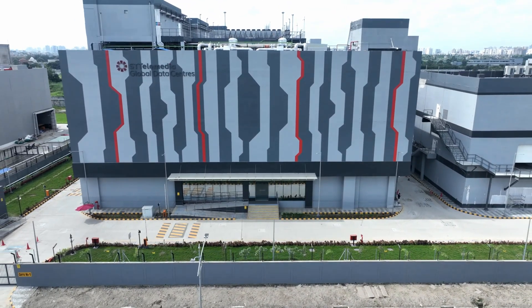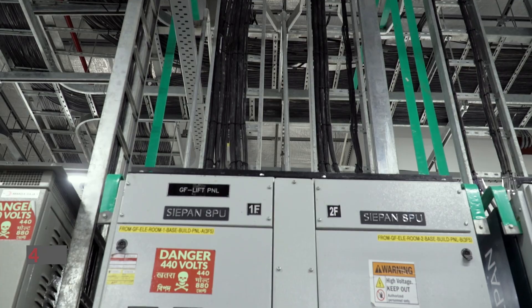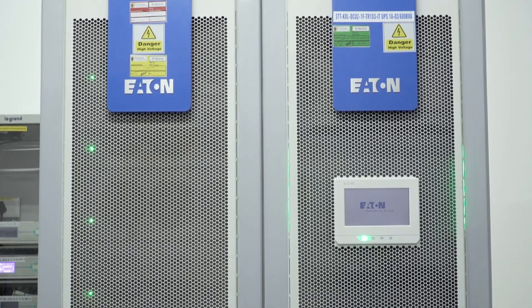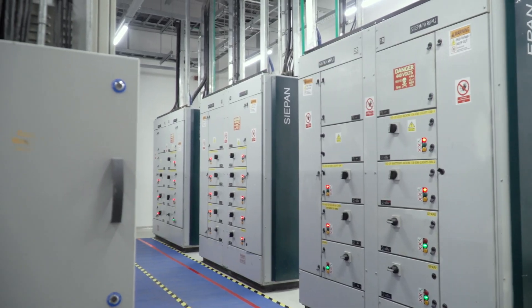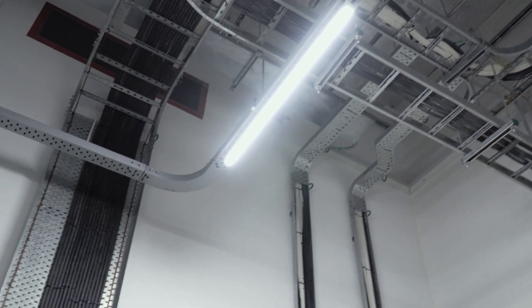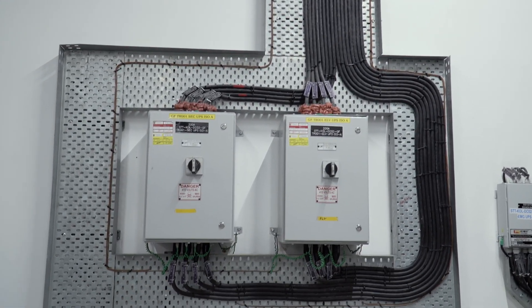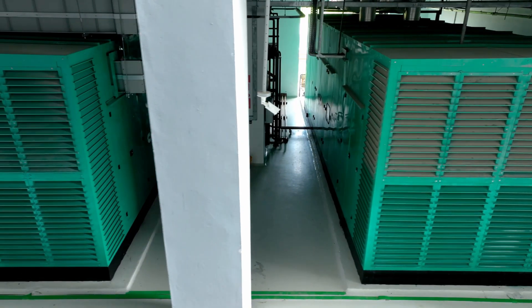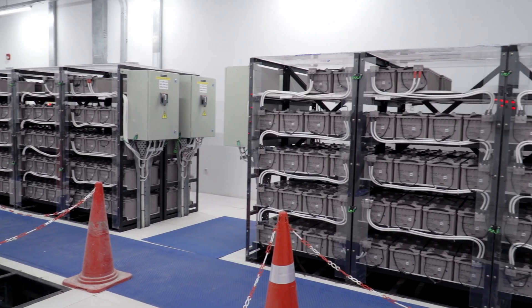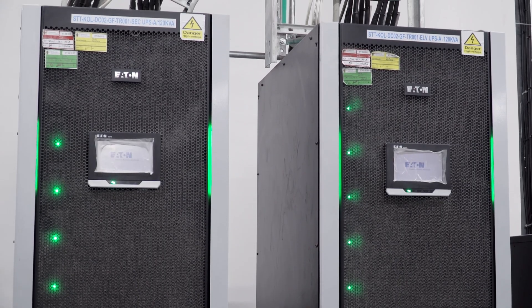Our next-generation data center campus is purpose-built for AI and high-density workloads, offering an initial 6-megawatt IT power, expandable to 18-megawatt IT load. Anchored by 33 kV lines for stable, high-capacity utility integration, with an N+2C configuration and radial N+N main power incomers for continuous operation. Type-tested compact substations, low-voltage diesel generators, and N+N redundancy from UPS to rack level ensure uninterrupted availability for mission-critical AI operations.